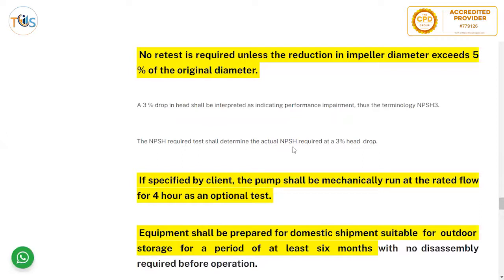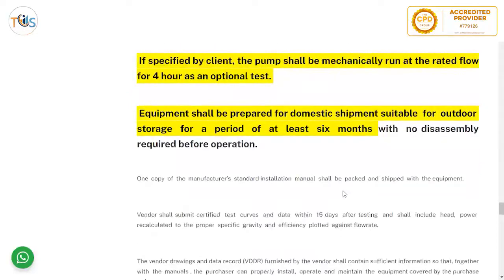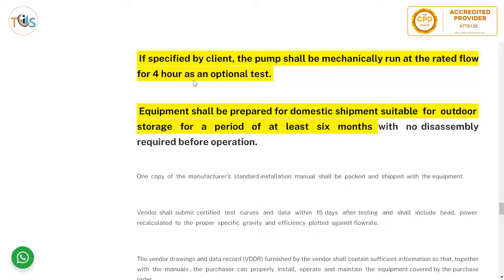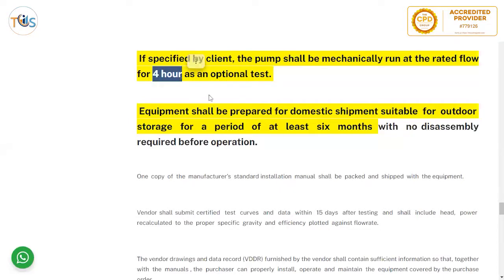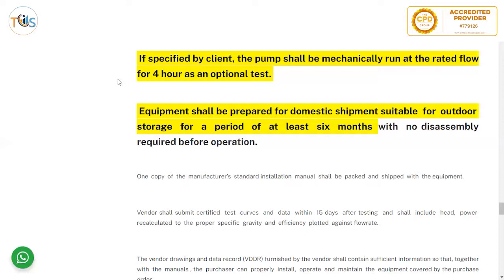The NPSHr test shall determine the actual NPSH required at a 3 percent head drop. If specified by the client, the pump shall be mechanically run at rated flow for four hours as an optional test. The client normally pays for this additional assurance; every 15 minutes the vibration, temperature, and pressure are checked. This is called a mechanical running test and is expensive and time-consuming as it requires connecting inlet and outlet and creating a fluid loop on the test bench.